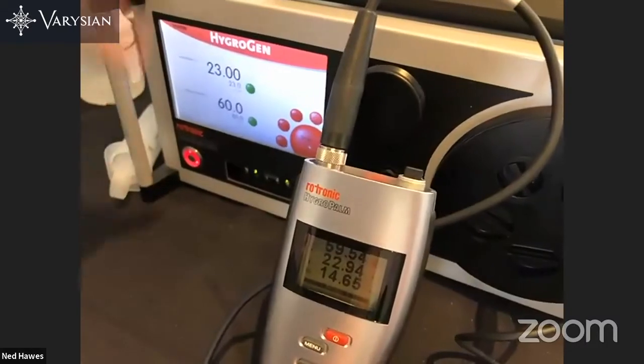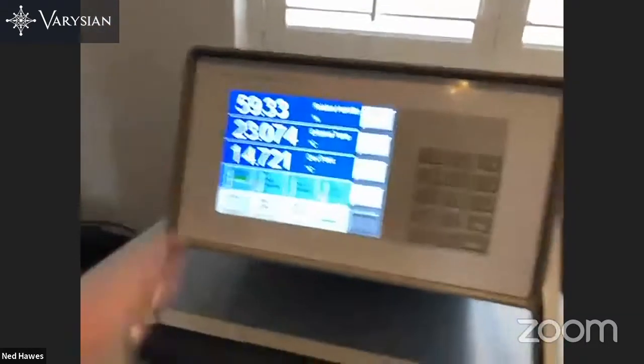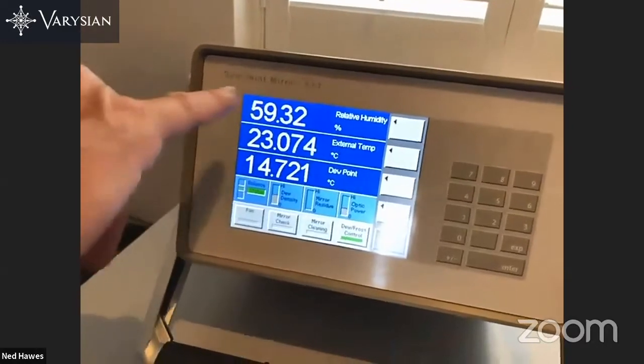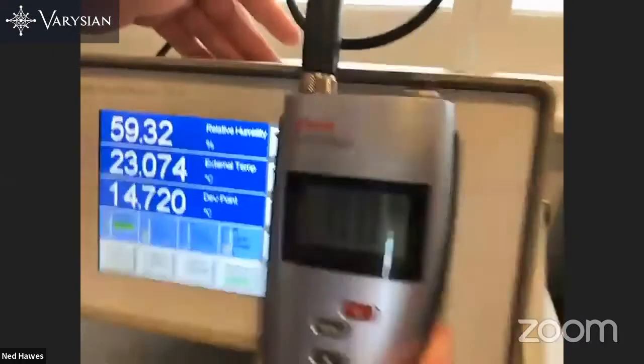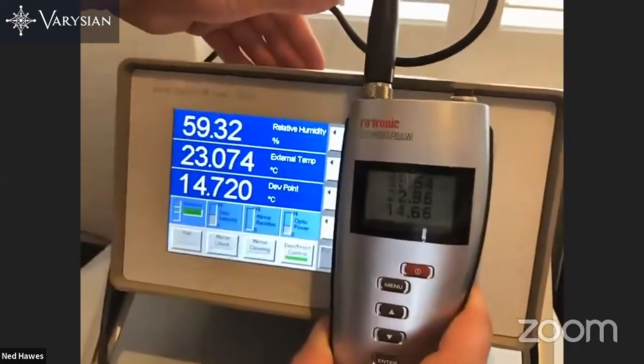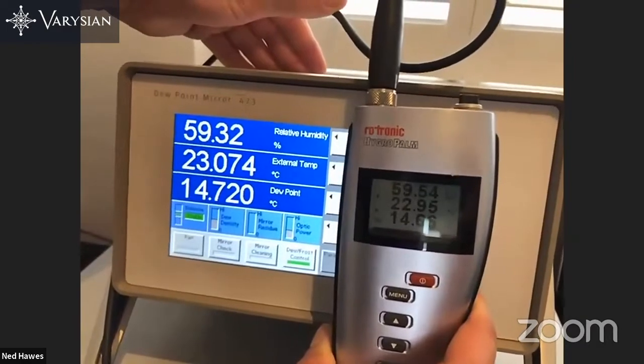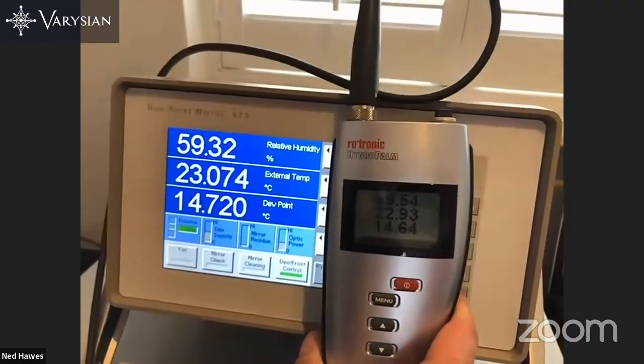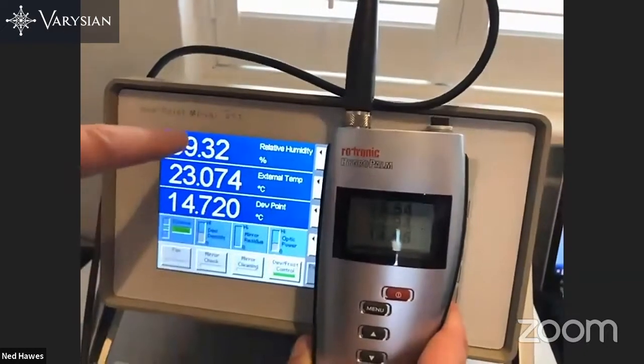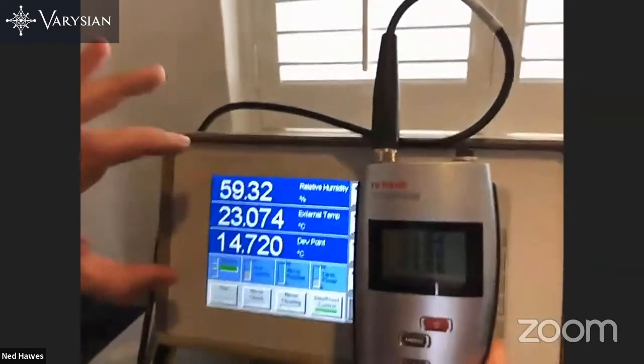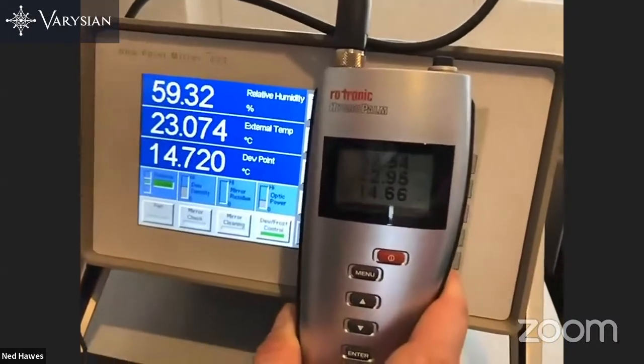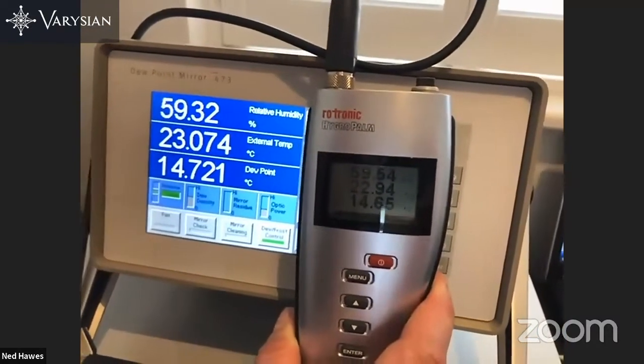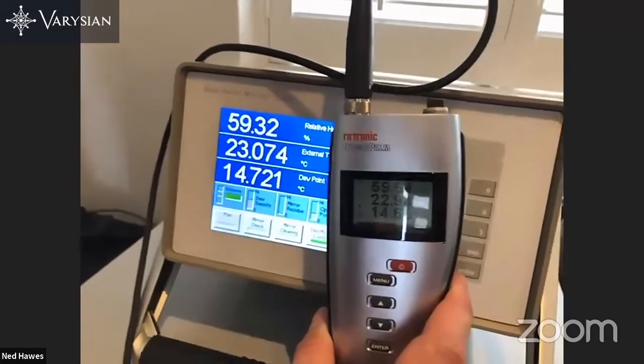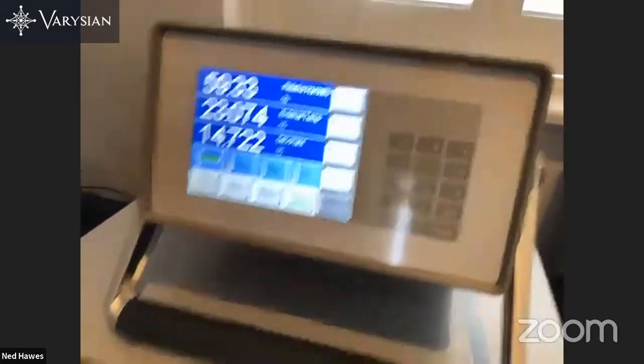Obviously, each of the numbers is different. So we then have what the MBW is reading via the RP2 head. Just to compare the two, we've got 59.54 versus 59.32 on a generated value of 60. Now, the number that we want to compare is this number against this number. This is your reference number. This is your calibrated, traceable to national standards number, as opposed to the number on the generator on the HygroGen itself down here, which is just for indication only.